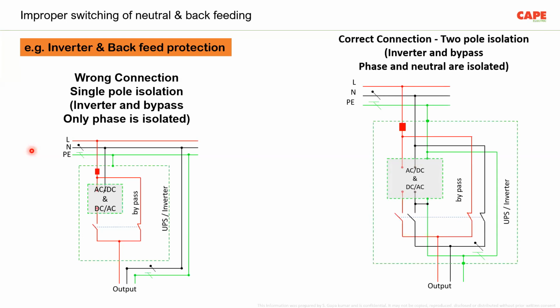What is actually recommended is that both the phase and the neutral have to be isolated. That means the circuit which is fed by the inverter shall have both the neutral and the line conductor, either from the inverter or through the bypass. So you cannot loop the neutral just like that, take the neutral from a neighboring circuit and use it in your circuit. This is actually illegal. You cannot do that.